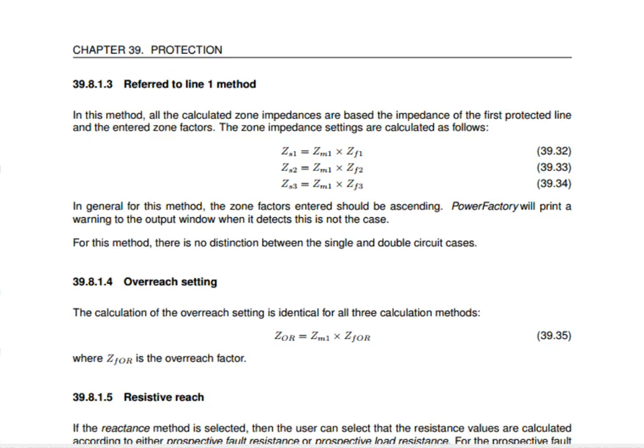The third and final method is known as the referred to line 1 method. Here you can see that all the zone reach settings depend on the impedance of the first line. Different zone factors are applied for each zone calculation.